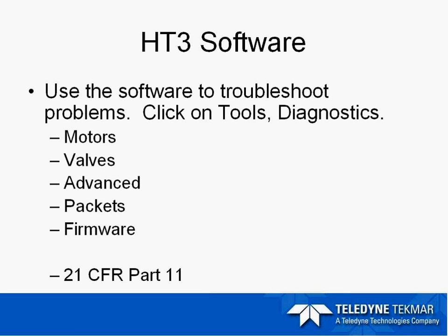There is also a Firmware tab, which allows you to flash upgrade the CPU board with programming to the latest version. If a problem or enhancement is identified, firmware files can be downloaded to upgrade your system. Another feature of the HT3 software is 21 CFR Part 11 compatibility, selected when the software is loaded. This gives you independent control of functionality per user — you have an administrator who can set up individual users and give permissions for access to different parts of the software. It keeps a record of each user and what they have done in the instrument. The hold button and step button are disabled due to 21 CFR Part 11 compliance requirements.